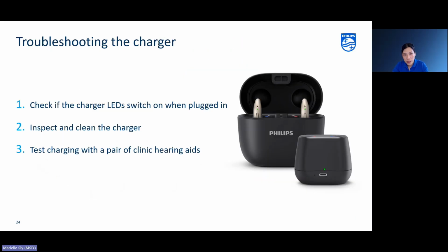And if you've determined that the hearing aid is perfect and functioning, it's time to troubleshoot the hearing aid user's charger. Just follow these simple steps. The first one is to check if the charger LED lights switch on when they are plugged in. If not, you can try changing the USB cable, or you can also change the adapter plug if it's possible. And then you can also try another wall outlet. And if the user's charger is still not turning on, then it will need to be sent back to repair.